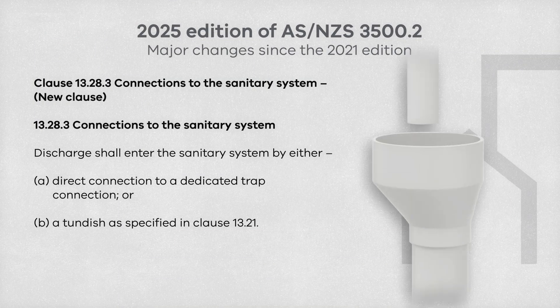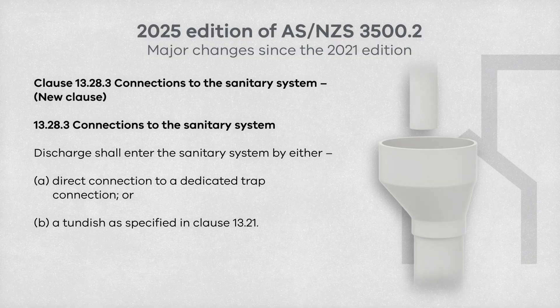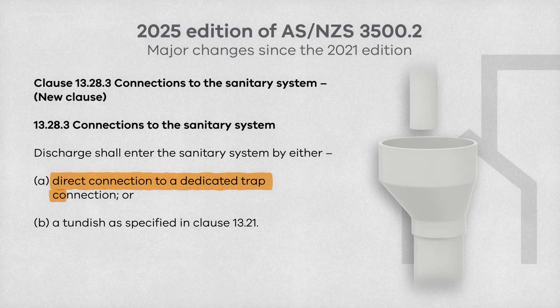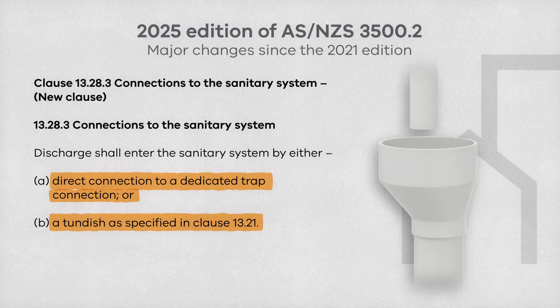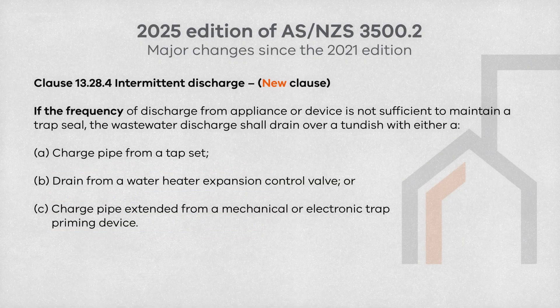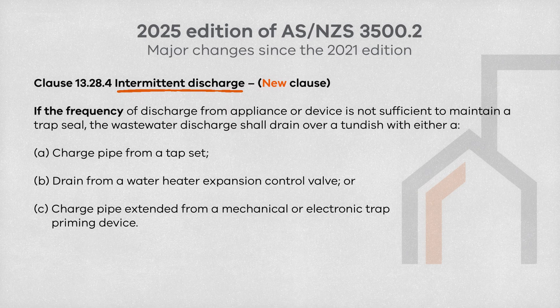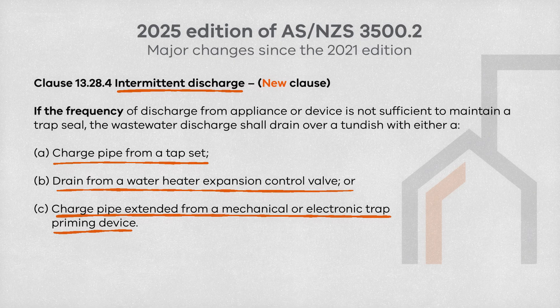The new clause, 'Connections to the Sanitary System,' specifies that discharge must enter the sanitary system either through a direct connection to a dedicated trap or via a tun dish. The clause on 'Intermittent Discharge' has been added to outline three requirements for cases where a device does not discharge frequently enough to maintain a trap seal. These updated requirements are now displayed on screen.